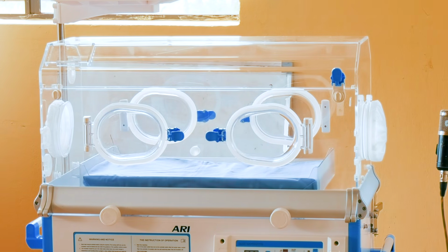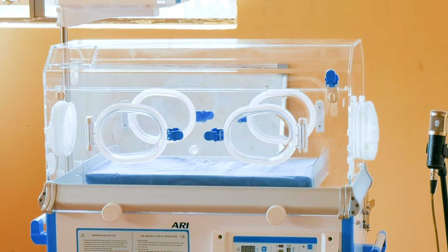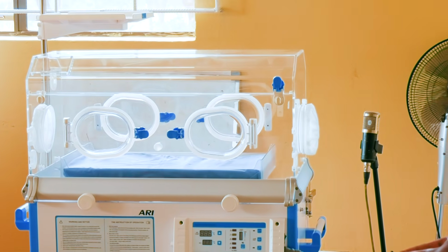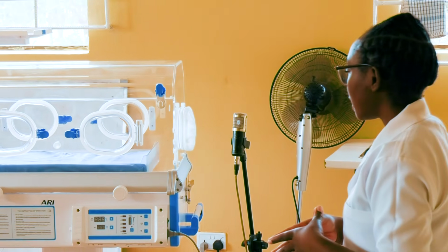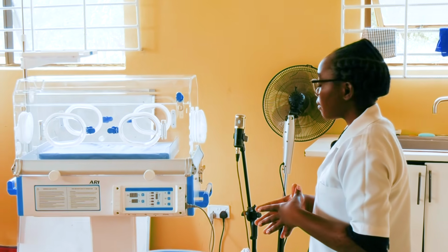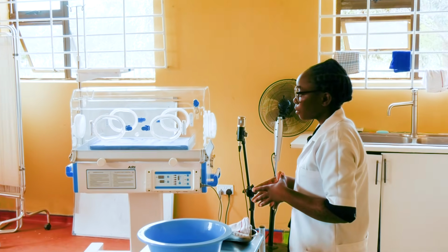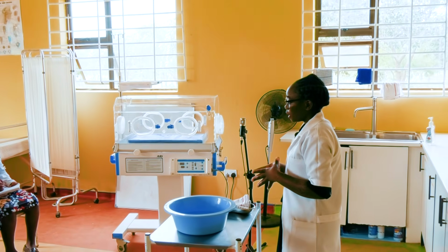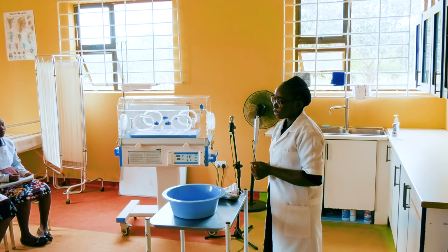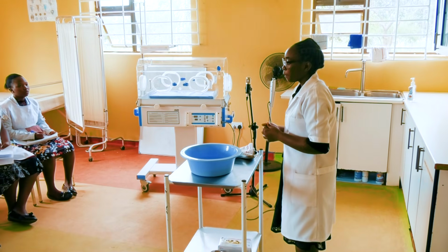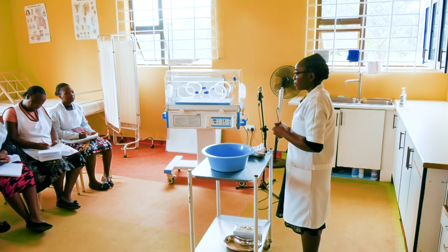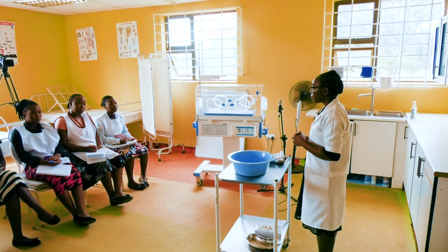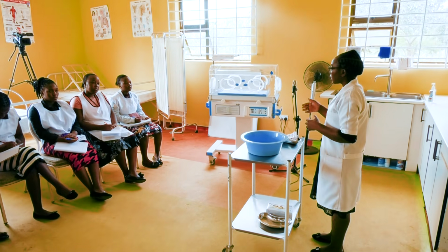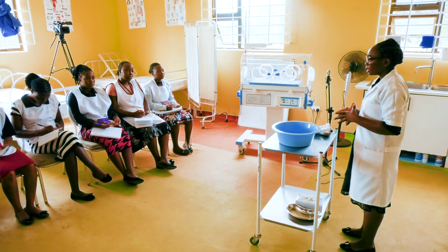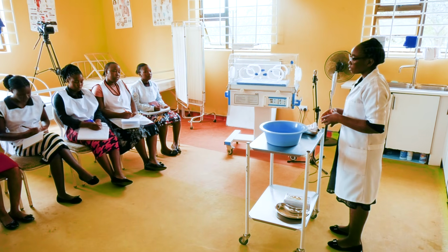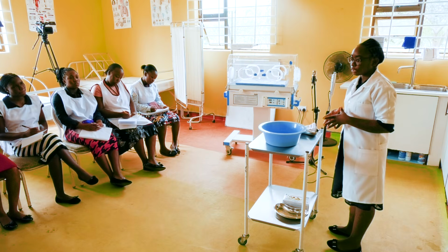Usually our ranges start from 25 degrees Celsius up to 37 degrees Celsius. When it's greater than 37, the machine will give us an alarm and regulate the temperature. When it goes up to 38 degrees Celsius, it's too high for the baby, so the machine will switch itself off automatically, or there will be a cut off of power supply. The maximum temperature it can go to is 42 degrees Celsius.